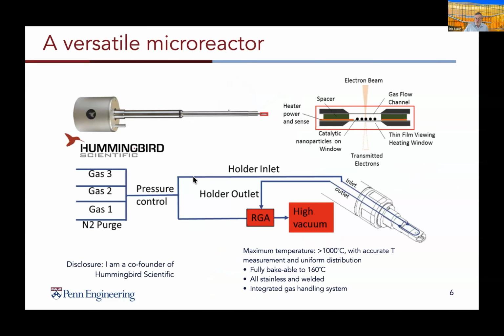We utilized some systems that we developed at the company Hummingbird Scientific. In this case, we build systems which again have heating elements embedded within them. They can go to 1,000 degrees Celsius easily. We have methodologies for measuring the temperature and making sure that it's uniform across the sample. Also, when we built the system, we made sure that it was a good catalytic reactor, meaning it's fully bakeable and stainless welded so that you end up having a good overall gas handling capability.